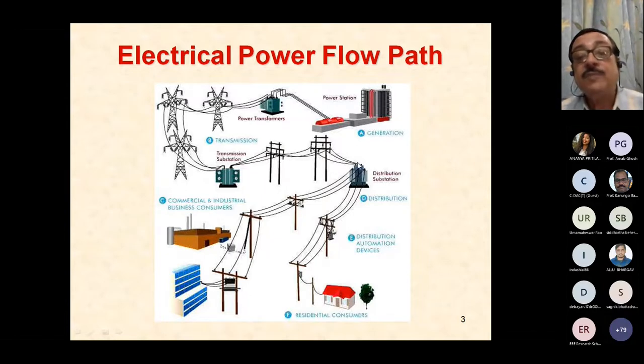What we do most of the time is we operate our semiconductor devices at a lower bus voltage, and then we connect it to the supply lines using a transformer, so that the power semiconductors operate on the lower voltage side and the main line is on the higher voltage. So we do connect it to 11 kV or 33 kV, but most of the time we talk about connecting it to the 400 volt line. Both can be done and both are being done at present.